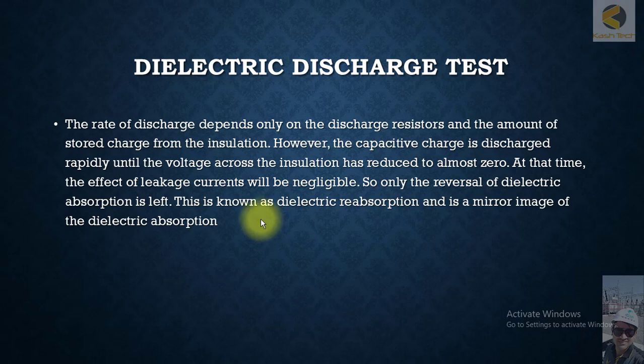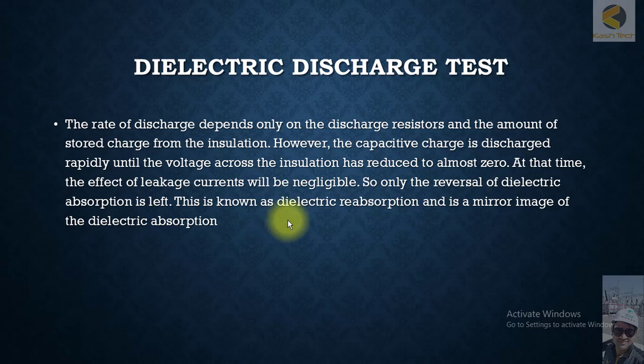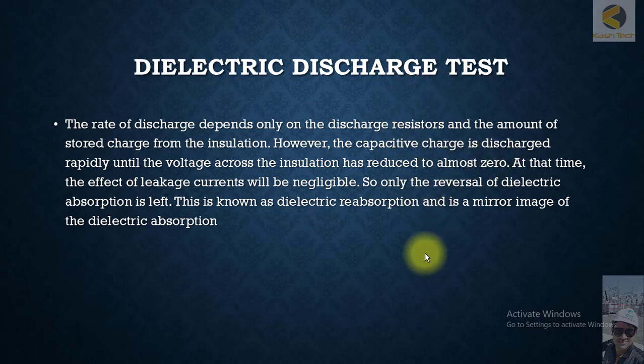The concept is: when you are doing insulation testing by normal method, you are basically measuring the charging current and absorption current at the same time, and the reading is not very stable. But when you are doing the discharge test, after some time the charging current will decay — there is no resistive or conductive charging current. So what remains at the end is the polarization of the specific insulation. You can check the chemical properties of the insulator, which also depend on moisture and other factors.